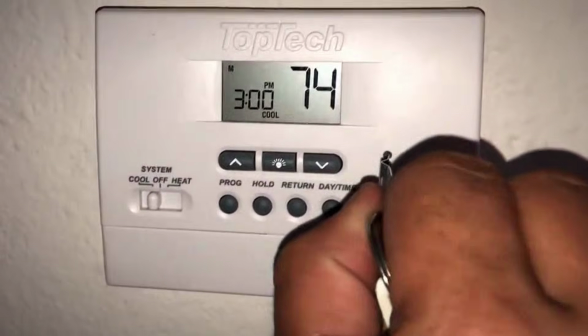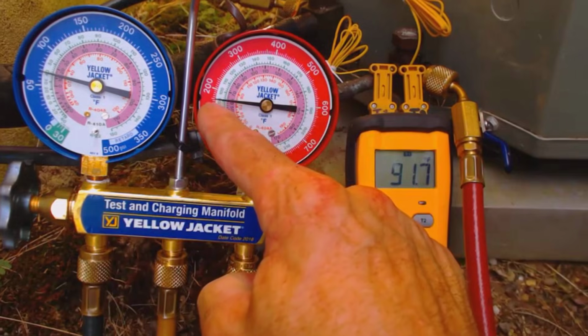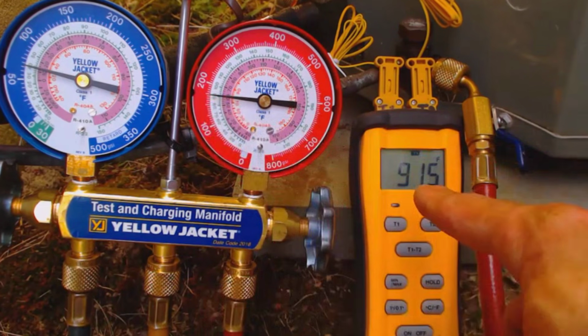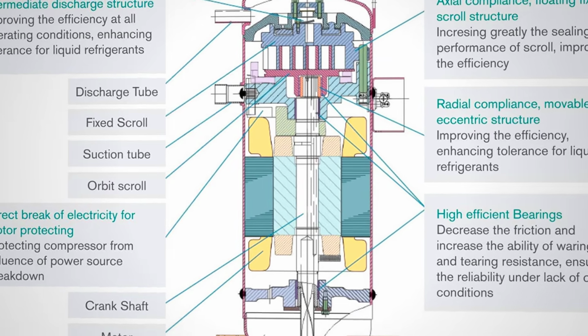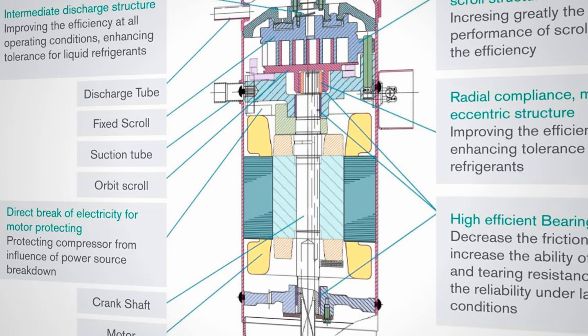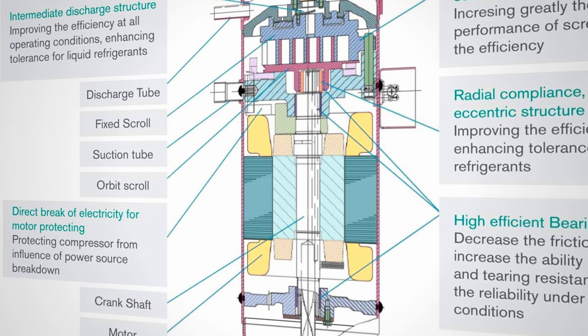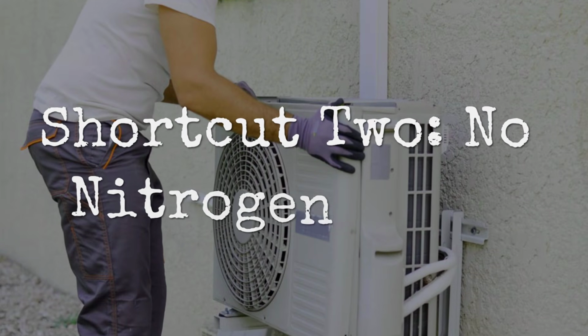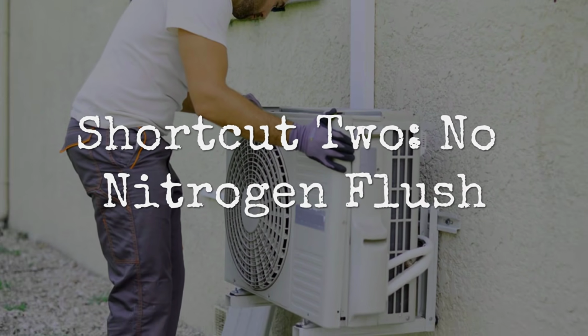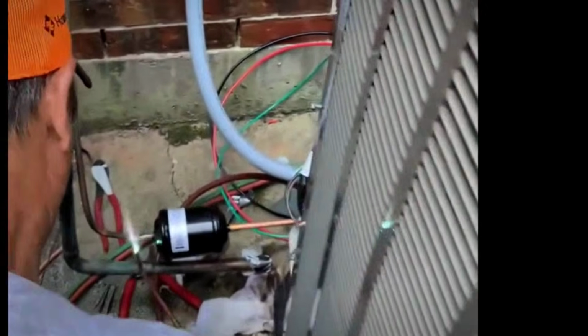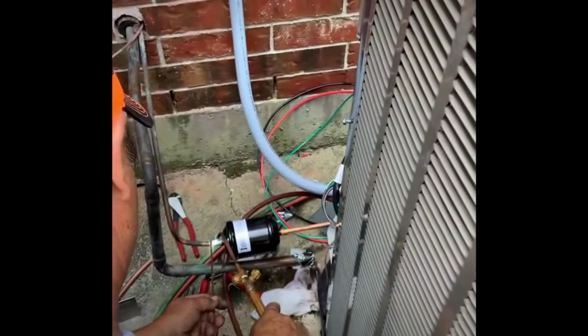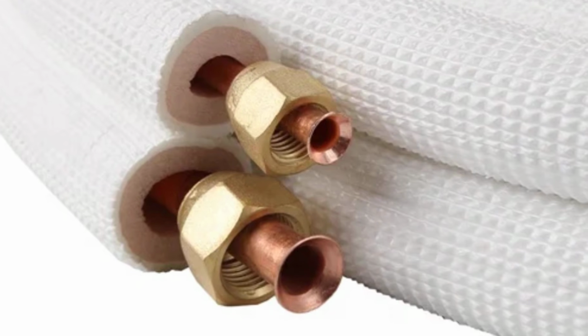By the time you notice the unit is not cooling properly, you have lost most of your refrigerant charge and the compressor has been running in a low charge condition long enough to accelerate internal wear. Shortcut 2. No nitrogen flush. Before a refrigerant system is charged, the pipe circuit should be flushed with dry nitrogen to remove moisture and contamination from inside the copper. On a rushed installation, this step gets skipped.